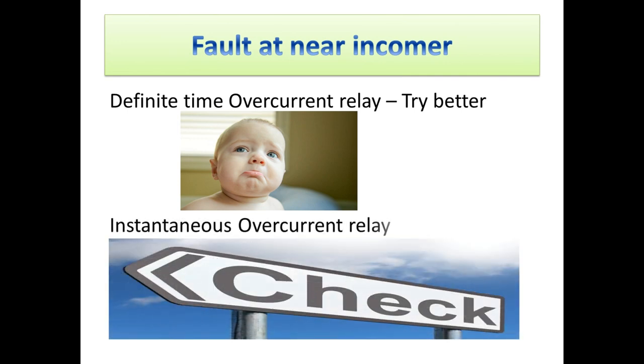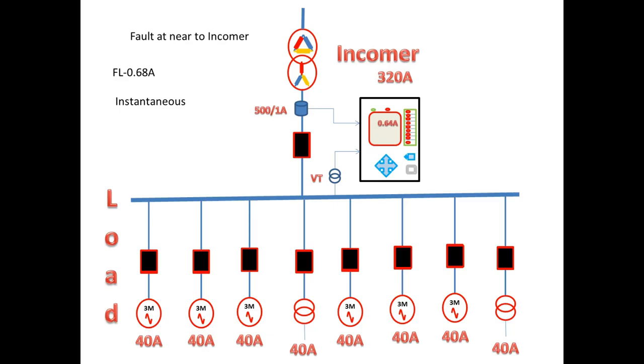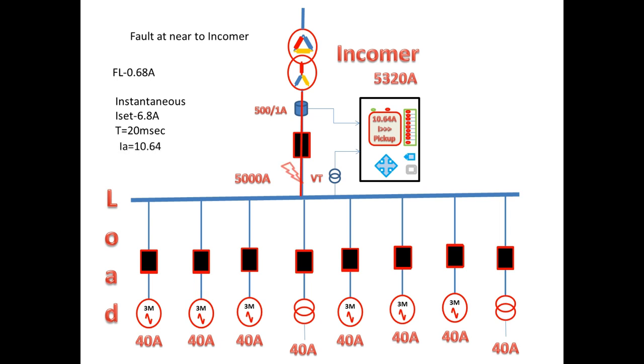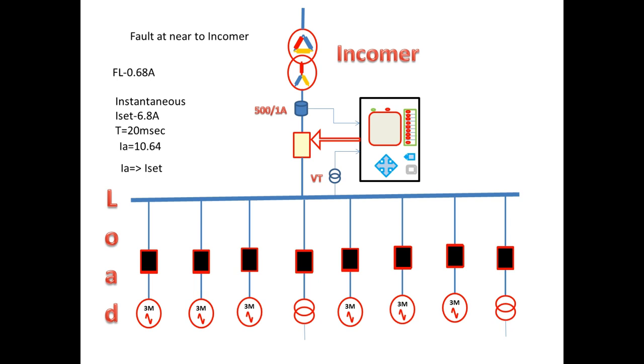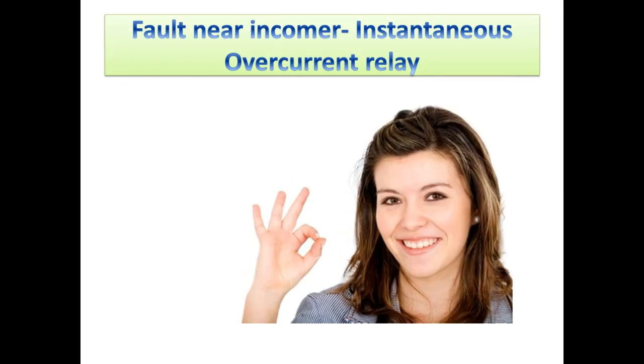For better protection I am going to check with instantaneous over current. For this I am going to keep ISET equal to 6.8A and trip time is 20ms, which is approximately 0 seconds. We consider the same sudden heavy fault occurring nearer to the incomer with a fault current of 5000A. The secondary current is also 10.64A, which is greater than ISET. The relay will pick up and trip instantaneously and the fault gets isolated. Here the instantaneous over current relay is much more suitable for this location.